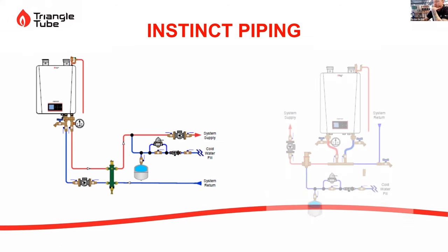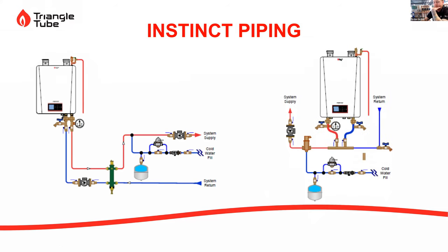So some piping applications. This is a quick PowerPoint that we use. I'll show you some stuff on the boards, but we have low loss headers and closely spaced tees. The only thing we really don't want to see in these boilers is a pipe straight in and out as an old boiler. There are some circumstances where we can do that with fan coils, where we're running, say, 1 inch to it, unlike the 110s. But we need to make sure that we size the pump properly, we have proper flow through that boiler, and we account for the head loss in our coil as well.